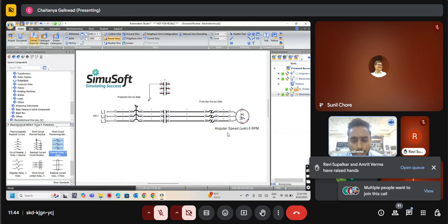Now I have to switch the direction. For controlling or switching the direction of the motor, I have to switch two phases of the motor, from L1, L2, and L3. The input to both contactors will be the same, but the output will get changed, so I'll just change this one.